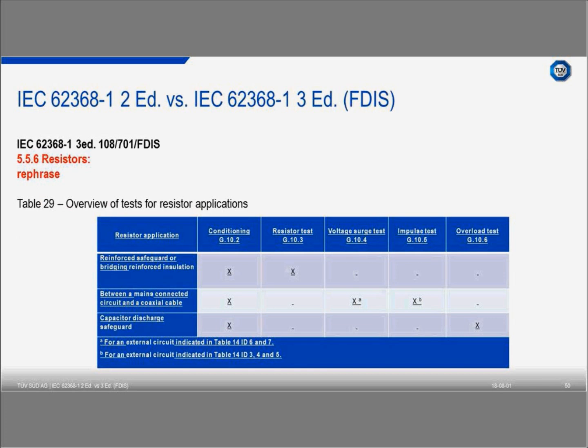This is a topic about the resistors. Table 29 gives you an overview of which of the tests from Annex G10 are necessary when we use a resistor for different areas. The point is reinforced safeguard or bridge reinforced insulation: then you have to go for the conditioning and the resistor test. And if we take the last one, cap discharge safeguard, then you have to condition and do the overload test. So this reduces the number of tests which you have to do with the resistor if you use it as a safeguard. And I think the most interesting point is normally the cap discharge as a safeguard here.